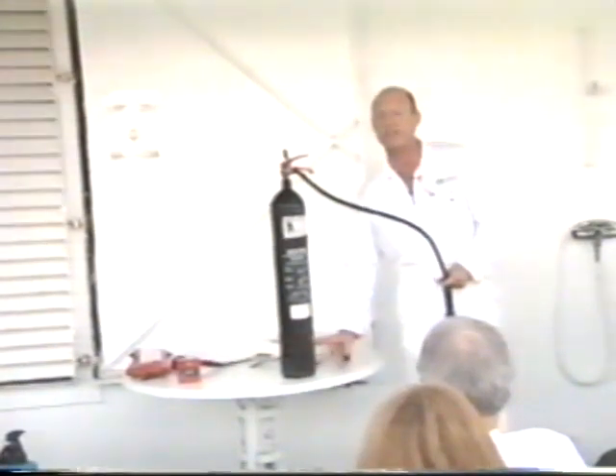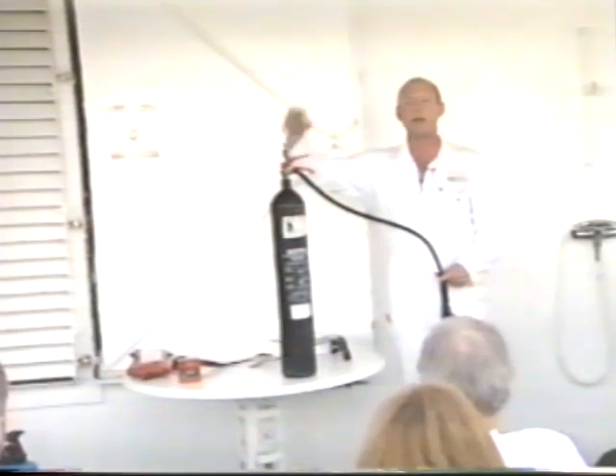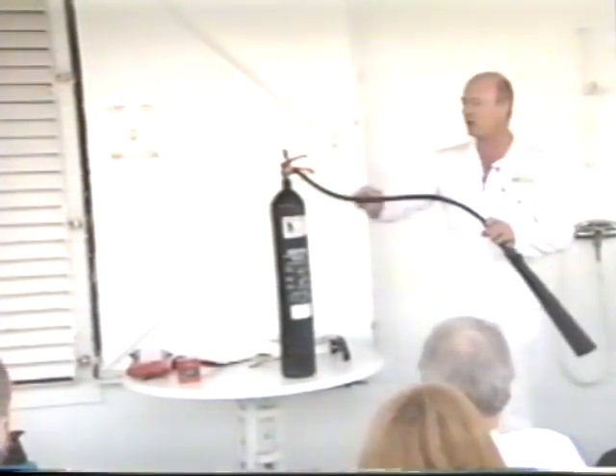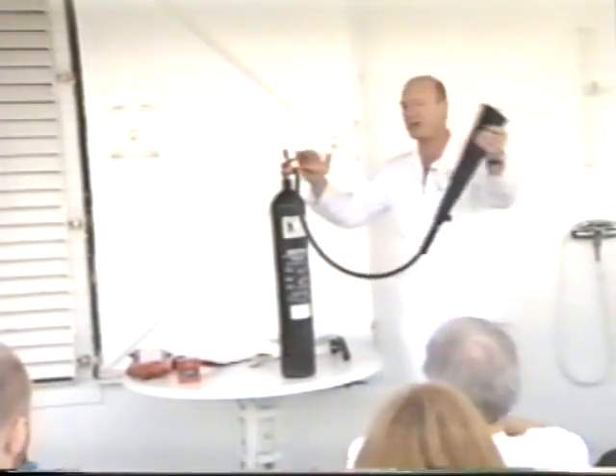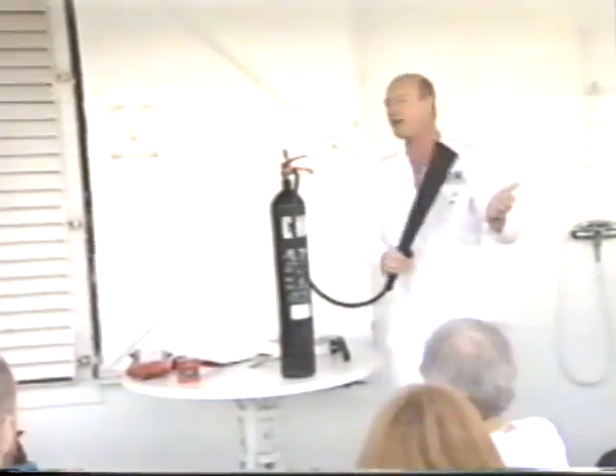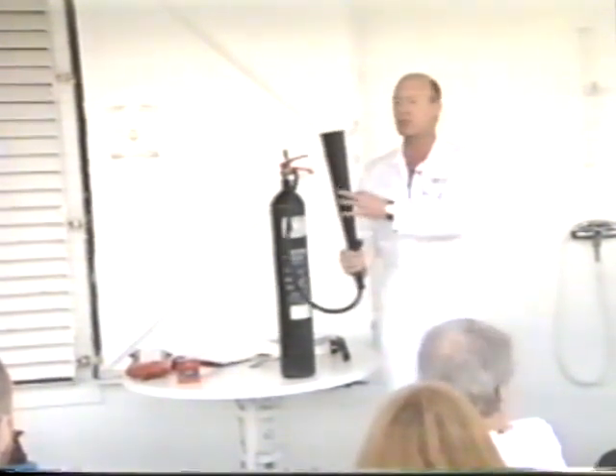All right, that is snow, that is ice. Don't ever touch it. These nuts and bolts arrangements here, they go white, all right, because that is also freezing over. This hose gets very cold, and the nozzle here, to about there, starts to freeze over as well. It goes white. If you put your hand there and operate this, when you go to take your hand away after the 20 seconds, you will leave 4 to 5 layers of skin on this nozzle. Please don't ever use it that way.